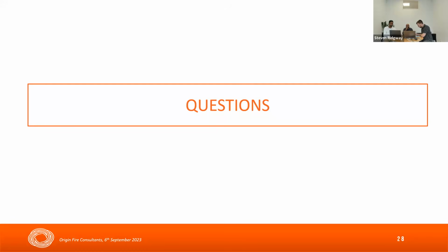Sweet. Thanks, Stephen. Next one, Stephen, do you think you can answer that? Do we need to design a fire wall supported by the floor as a cantilever for 0.5 kPa fire load? Is that structural engineering? Where that requirement is, your tested firewall systems will achieve the requirements. So I think it's AS 1530 Part 4 for firewalls. When they test those, they will put a degree of load on it and also some pressure.